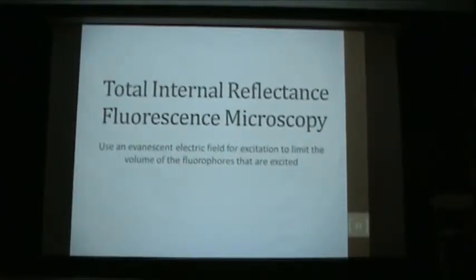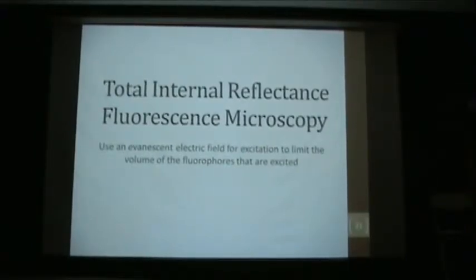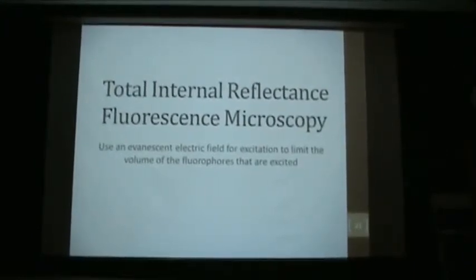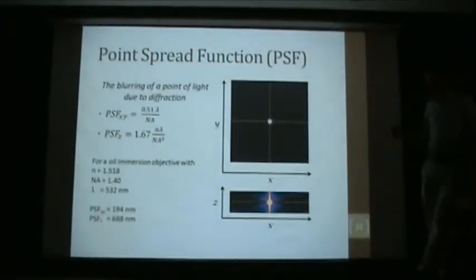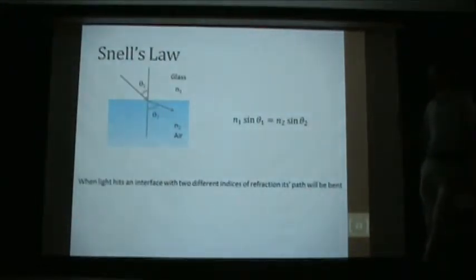Another technique is total internal reflection fluorescence microscopy, or TIRF. Here the light is totally internally reflected off the cover glass, and only an evanescent electric field penetrates into the sample — only about 100–150 nanometers. So only the sample within 100 nm of the cover glass is excited, and all signals come from that 100 nm slice. That 600 nm Z resolution we had is now collapsed to 100 nm — we're beating the diffraction limit in Z. The downside is your sample has to be within 100 nm of the cover glass.